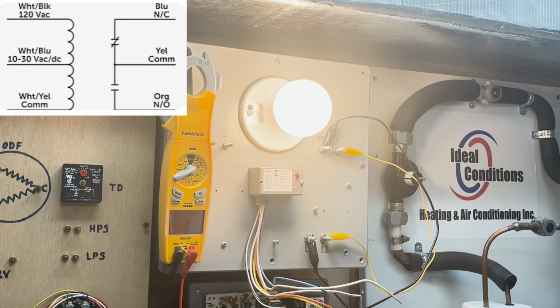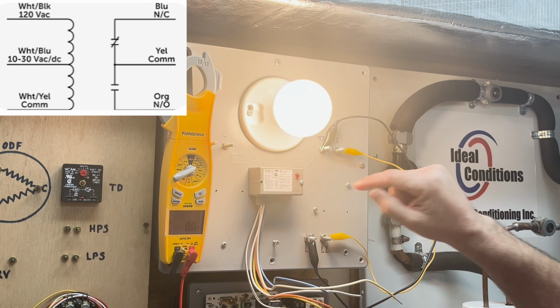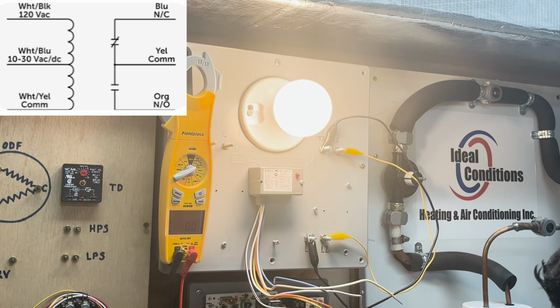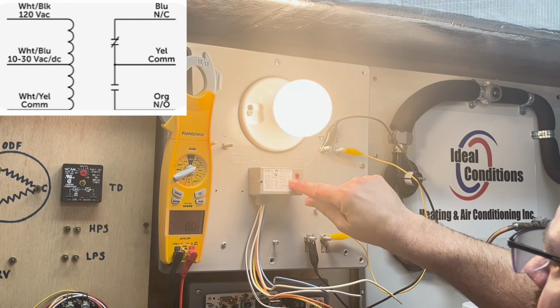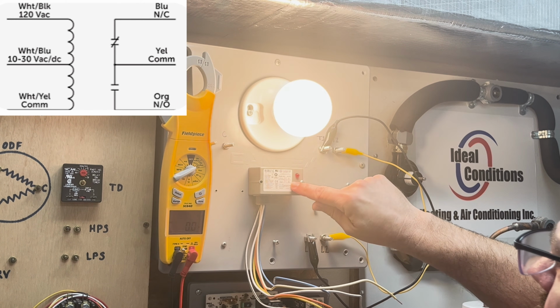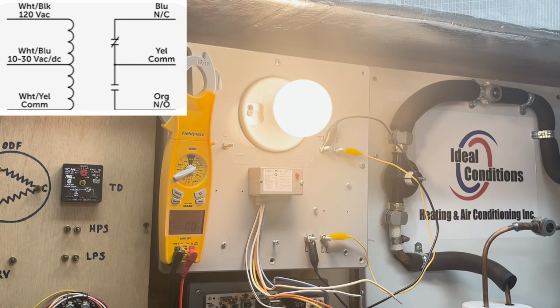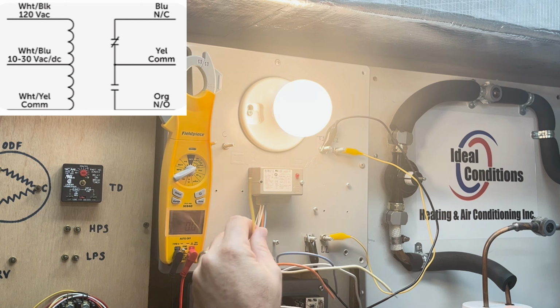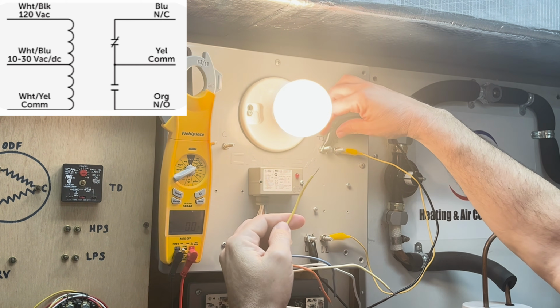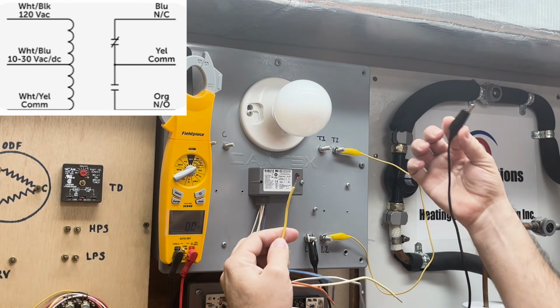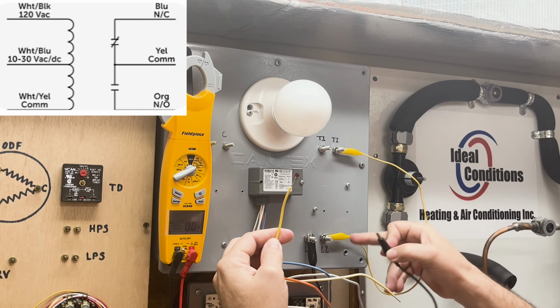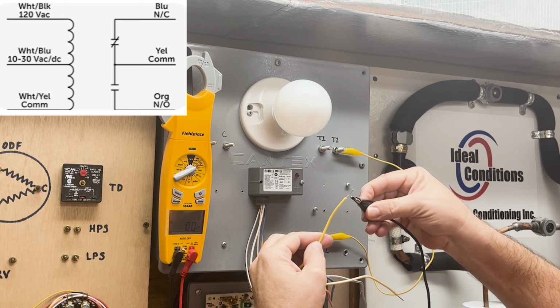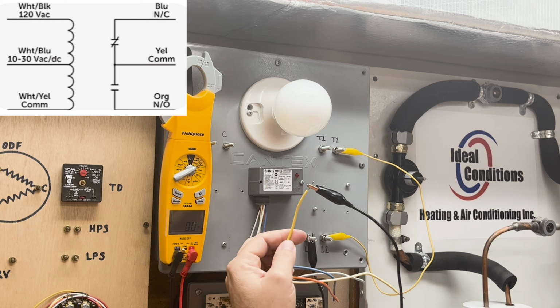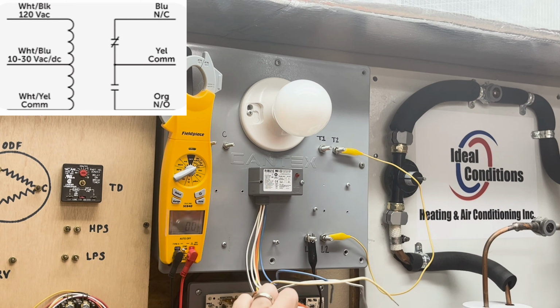So we're going to use this as our coil voltage, and then we'll demonstrate the normally closed and the normally open. So before I put 24 volts on it, normally closed would be blue and common would be yellow. So here's the yellow wire. And so to do this, that means I would take any leg of power, it doesn't matter if it was L1 or L2, that line voltage, and I'm going to go ahead and connect that to yellow because yellow is common. All right.